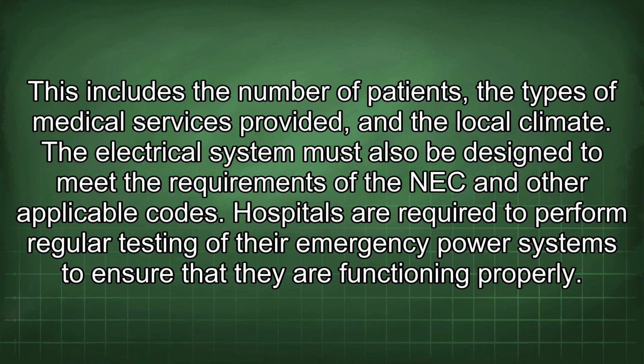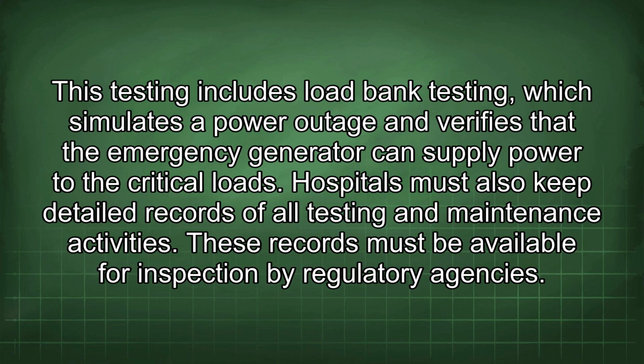Hospitals are required to perform regular testing of their emergency power systems to ensure that they are functioning properly. This testing includes load bank testing, which simulates a power outage and verifies that the emergency generator can supply power to the critical loads. Hospitals must also keep detailed records of all testing and maintenance activities. These records must be available for inspection by regulatory agencies.